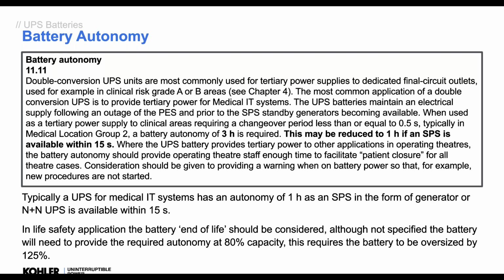Okay, the battery is considered to be end of life when it's got 80% of capacity. So that's not an hour, is it? You should be oversizing the battery to allow it to have an hour just before you change it at end of life. By doing that, we have to add on 25%, so size it at 125% from day one. Again, that's not going to be done unless you specify it.